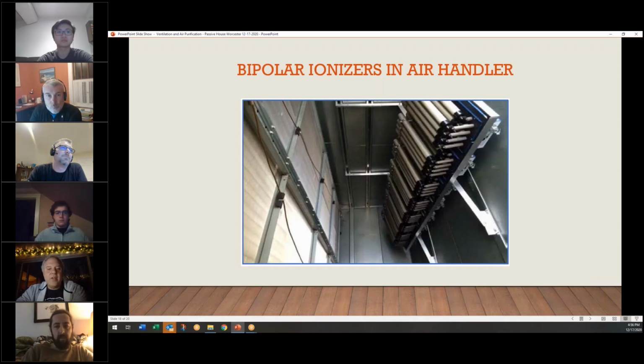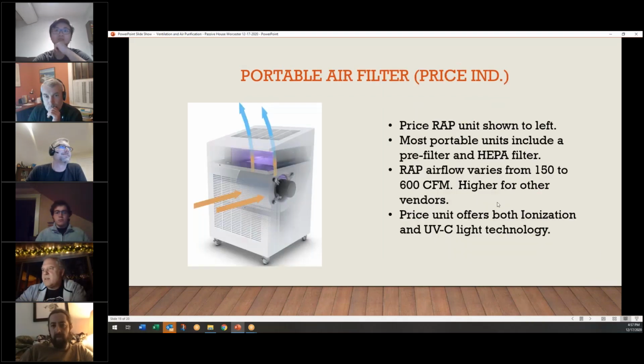And again, like UVC light, these have to be changed every 2 years. That's not the case with all ionization systems. There's needle point ionization, which doesn't really need that. However, there is some maintenance required with keeping the needle points clean. Otherwise, if they get dirty, they stop generating ions. And again, those two makers duke it out over who's got the best mousetrap, basically. So if you go to the next thing, I think this is almost the last slide.